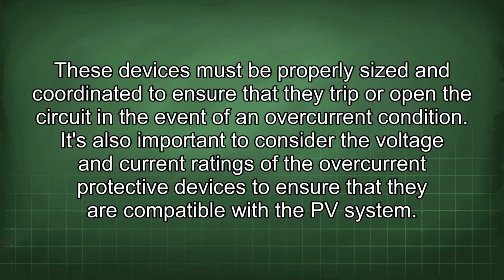These devices must be properly sized and coordinated to ensure that they trip or open the circuit in the event of an overcurrent condition. It's also important to consider the voltage and current ratings of the overcurrent protective devices to ensure that they are compatible with the PV system.